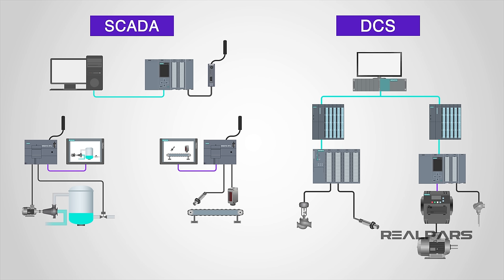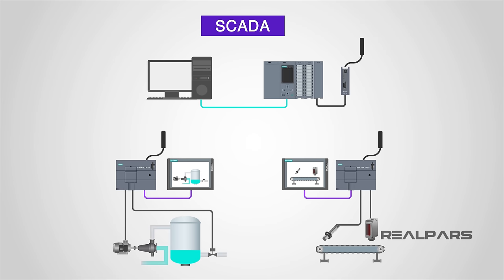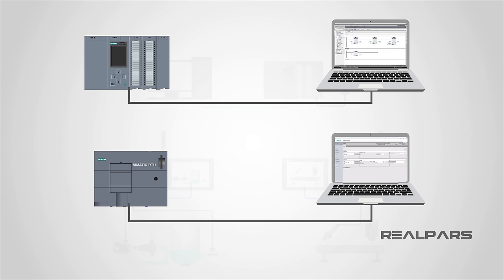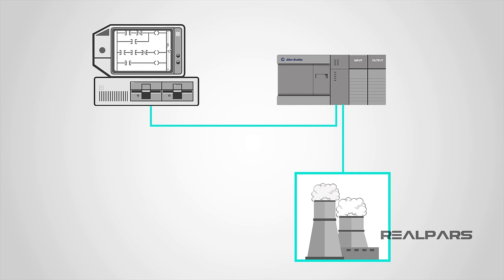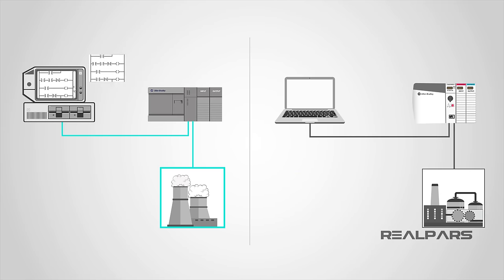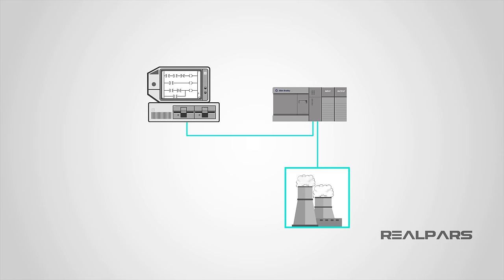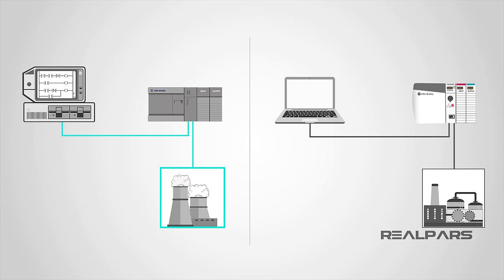Now let's discuss the brains of the operation. Within the SCADA system, there may be PLCs and RTUs. These components require programming in order to execute commands essential to plant operations. Earlier in automation history, there may have been thousands of lines of code to run a single process. Over the years, more ways to consolidate and reuse code have been implemented. This reusable code — custom function blocks, add-on instructions or AOIs — is written in the controller by a programmer and can be instantiated any number of times. It may take quite a while to develop a library of code that can be used over many projects.